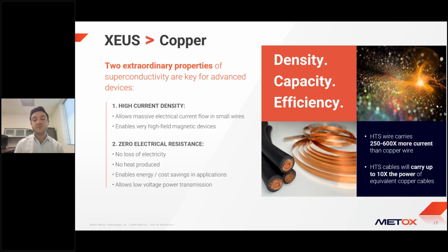The superconductor we use has a critical temperature of 77 Kelvin, the temperature of liquid nitrogen used as the coolant. At that temperature, there's zero electrical resistance, which results in no line loss in cables manufactured with superconductors. Those cables can carry up to 10 times the power equivalent of copper cables because the wire carries 250 to 600 times more current than copper on a cross-sectional area basis. You can see in the photo the comparison of what a copper wire cross-sectional area looks like versus a superconducting tape.